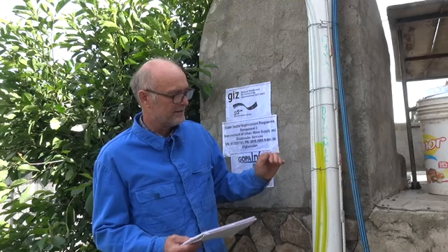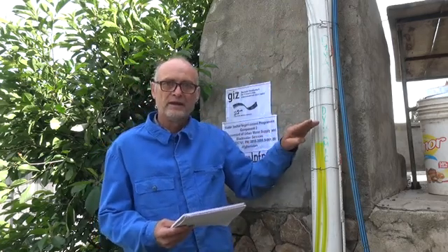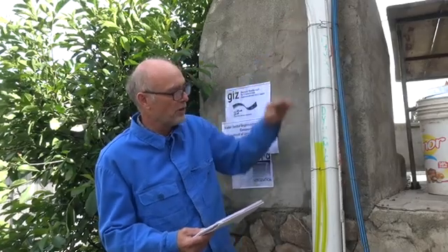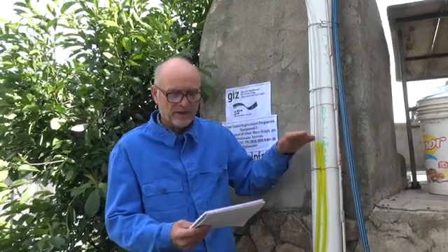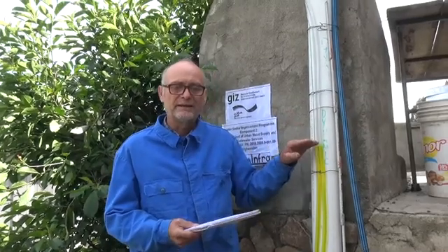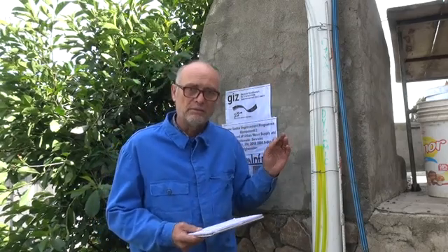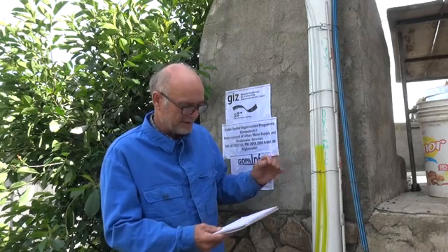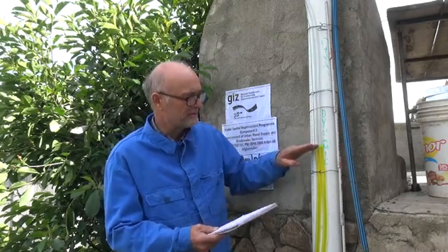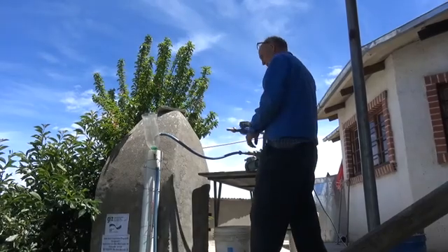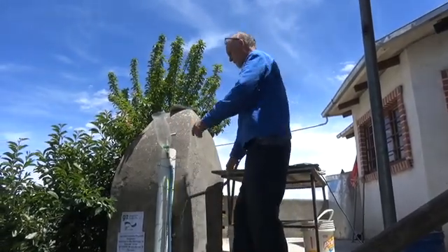So in this case, when the groundwater level drops, we have to check if another pump is necessary. Normally it is. So we have to use a smaller pump with more head and less flow. We have to make a test on our well, like we did now. We can do it also in our big well. We can make a test, and after this test, we have to determine which pump has to be installed. Now we dismantle the system and see how it works.